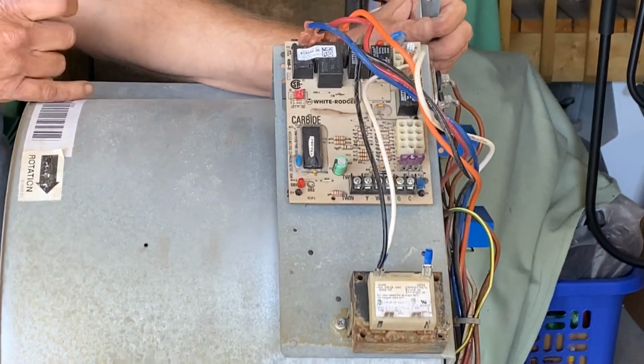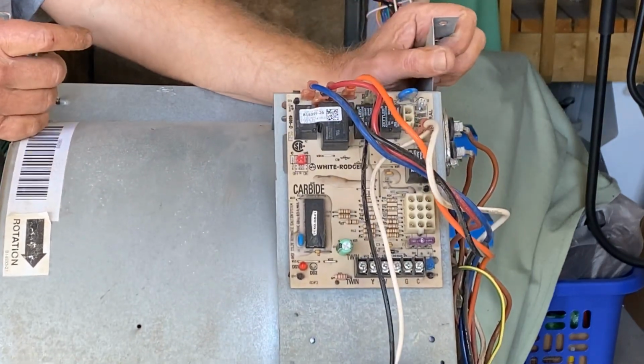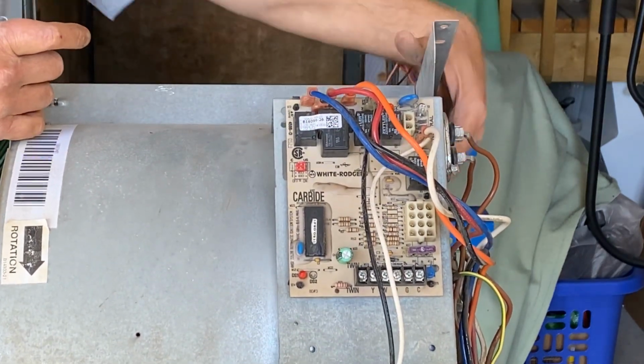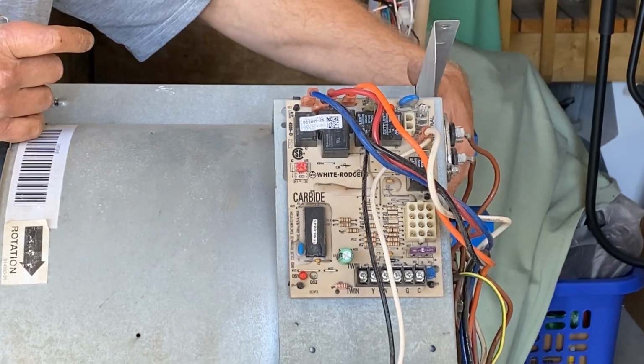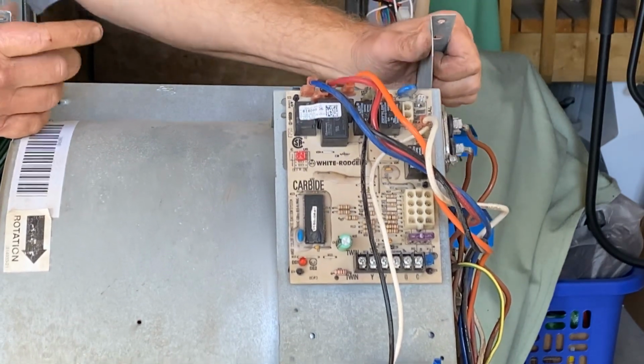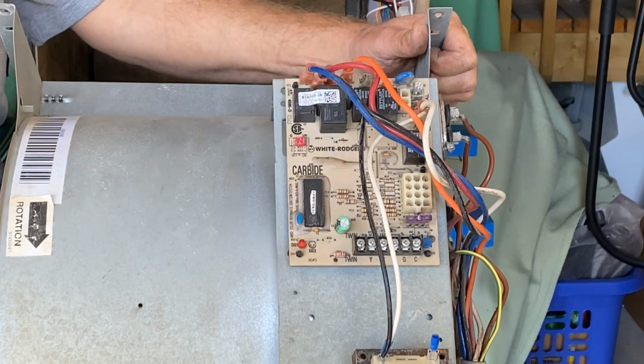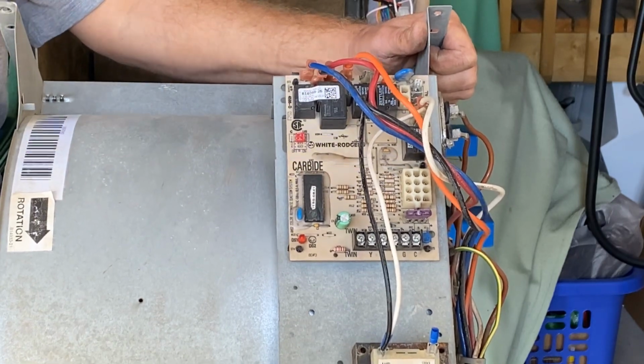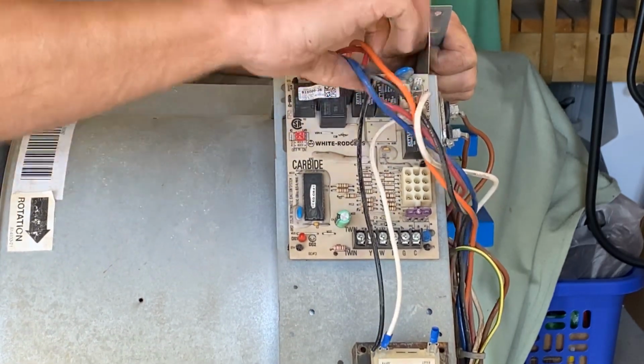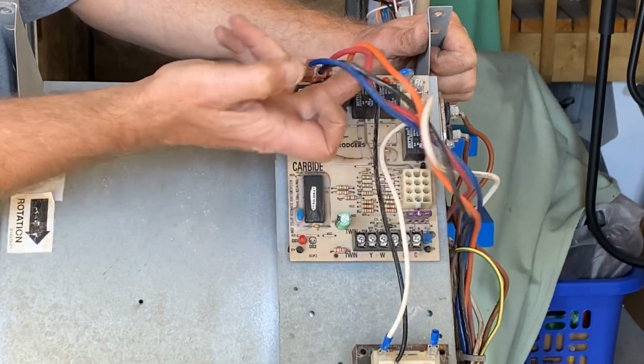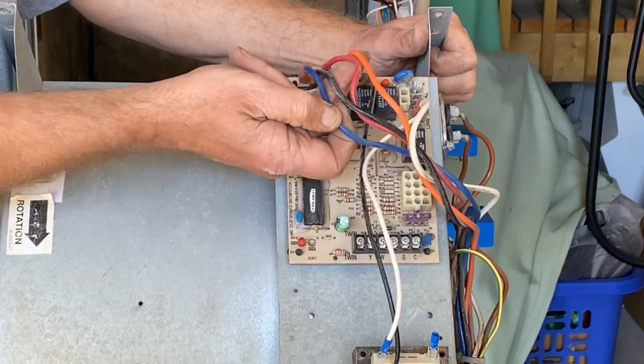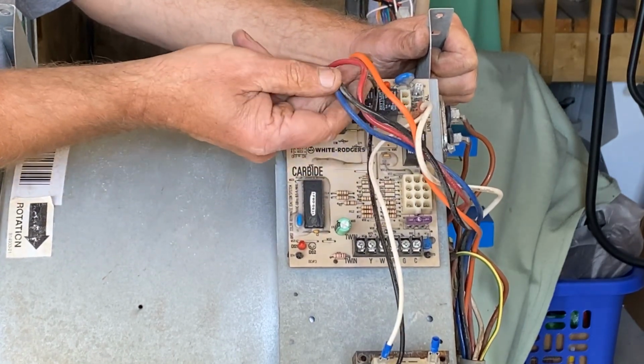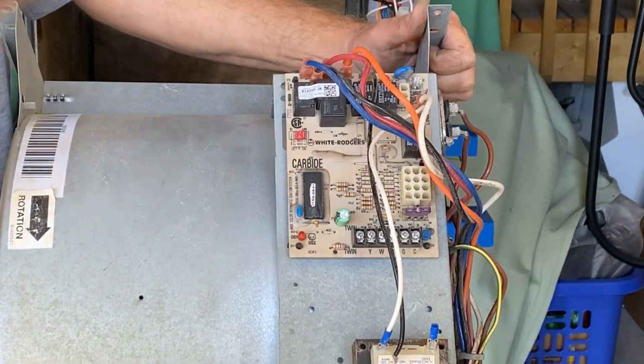The other thing to identify on this circuit board is this blower motor is a multi-speed motor. If you look in the wiring diagram, you'll see white wires are common, but there are actually 4 speed wires. I get to choose which speeds I want to run - me, the service guy, the installer, whatever.